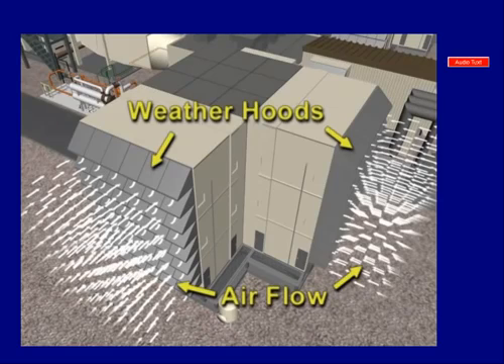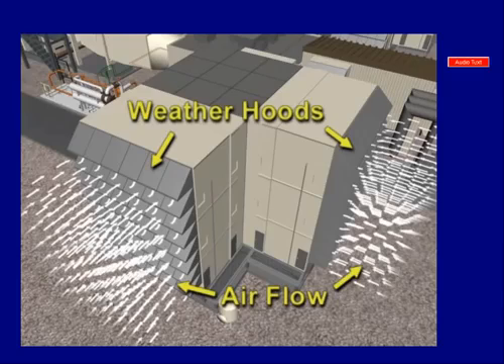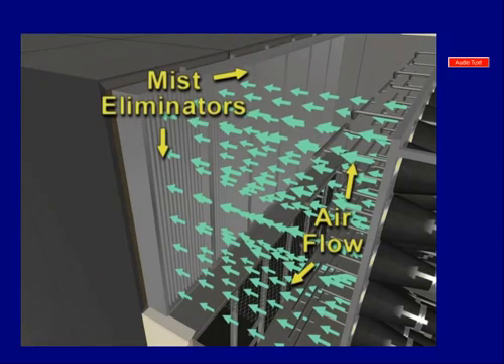Ambient air first enters the filter housing through a weather hood and screen that protects the filters from the effects of rain, sun, and debris. The air then goes through an evaporative cooling section that maximizes the gas turbine's output on hot or dry days. Downstream of the evaporative cooling are mist eliminators that capture moisture.